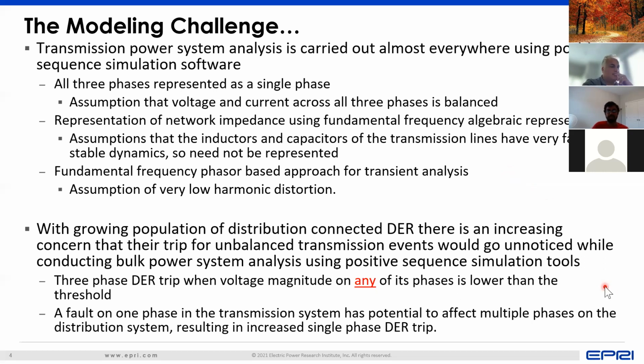But what happens with distributed energy resources is that this degree of imbalance, which is assumed to be low, can actually now be large. Even a three-phase DER can trip on unbalanced voltage, which means that even a small level of imbalance can cause a large amount of DER tripping. Also, single-phase faults are usually more common in the transmission system than three-phase faults. Thankfully, that is so, because a three-phase fault can cause a lot of damage.